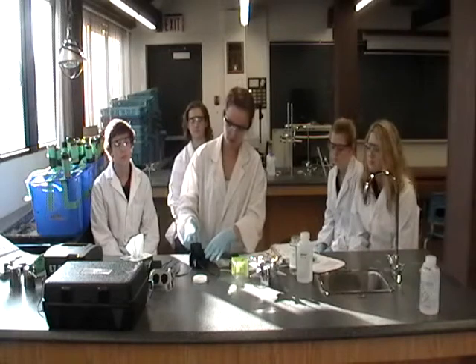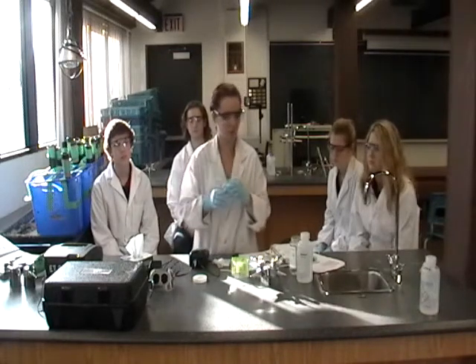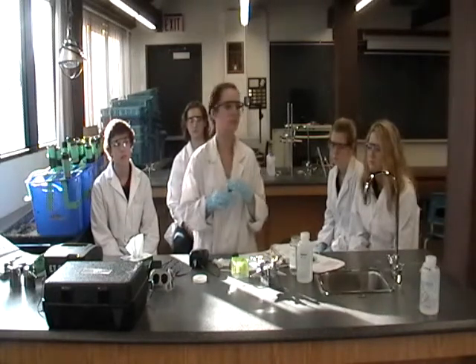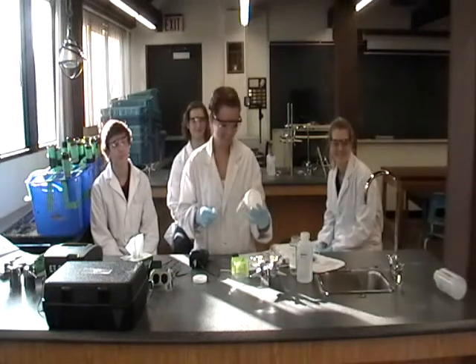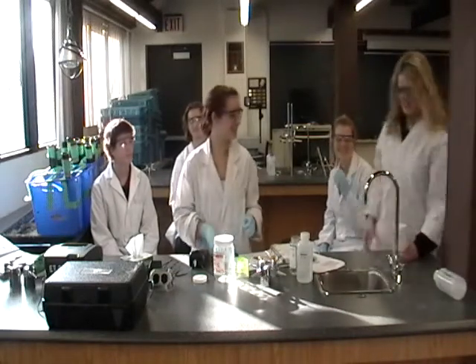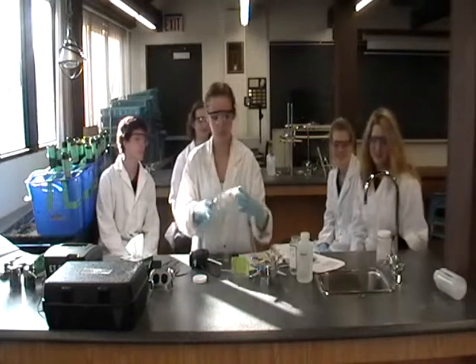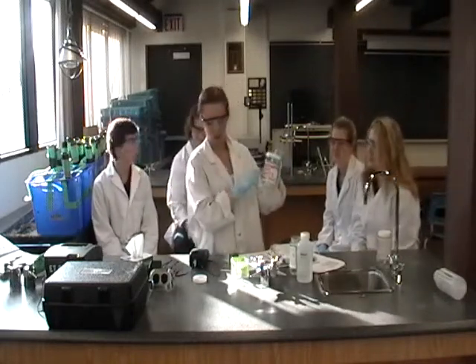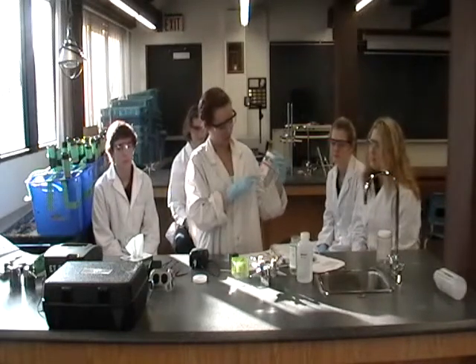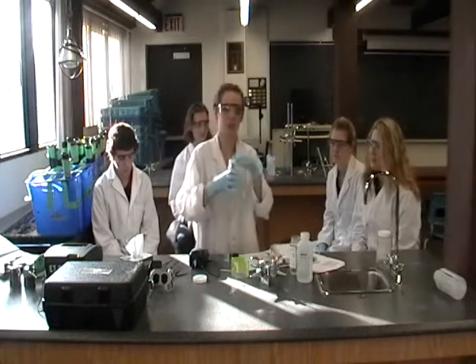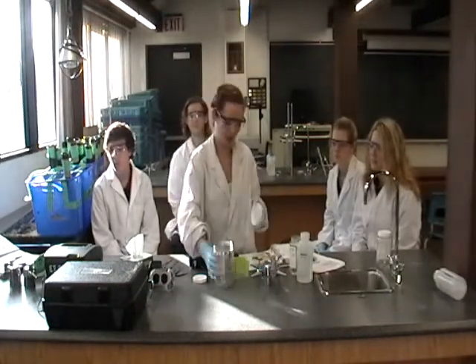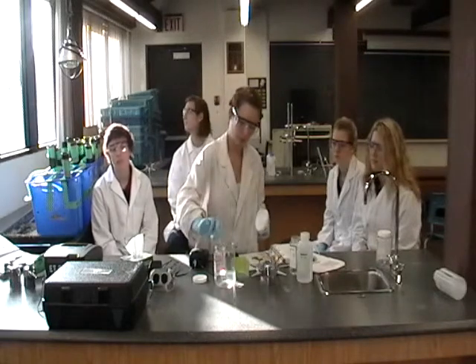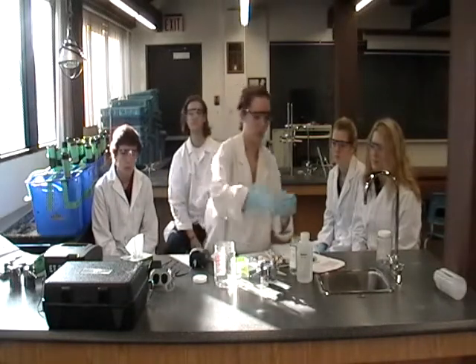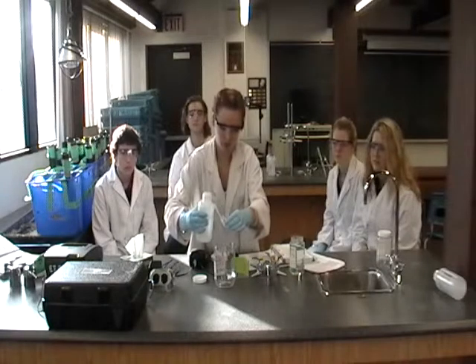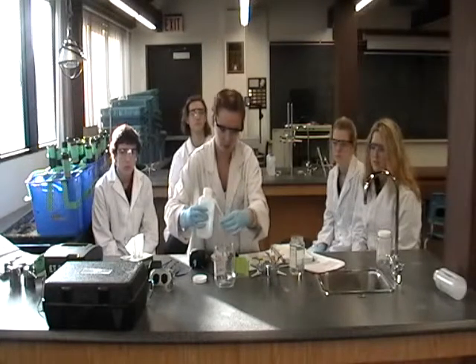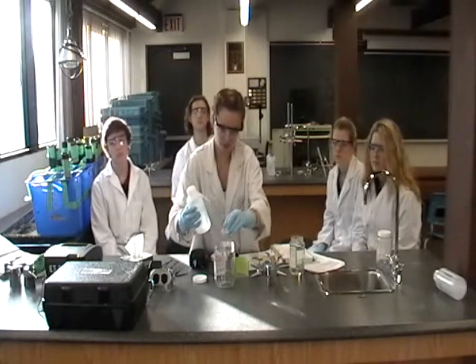So once we are finished this, we are going to put this in the proper waste container. So the proper waste container, it says the Lamotte, which is our meter, and the sulfate, and the number 3665. I want to make sure it's correct so we're not mixing any chemicals. We'll just put it in there, and we can rinse into here so that we're not getting any in the sink. Make sure that it's clean.